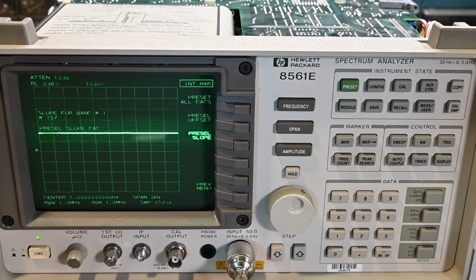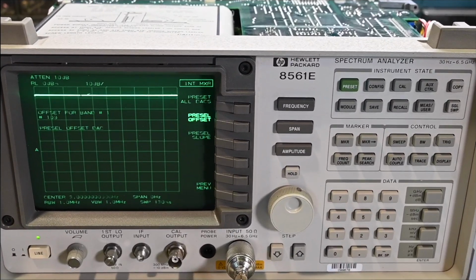So we've got that. Now it says to repeat steps 6 through 11 until both the slope and the offset are peaked. It says adjust the offset only at 3 gigahertz and the slope only at 6 gigahertz. So I'm going to repeat this several times to make sure that's peaked up, and then we'll continue on. I won't show that on the camera because it's the same steps I've just done. I'm just going to do them several more times.